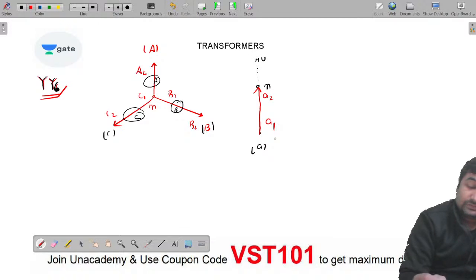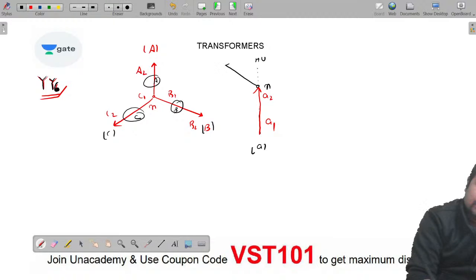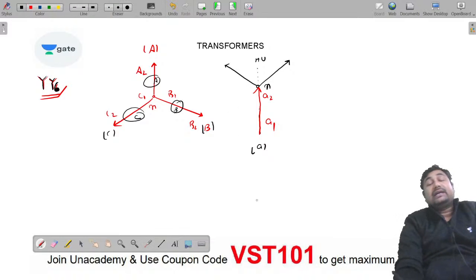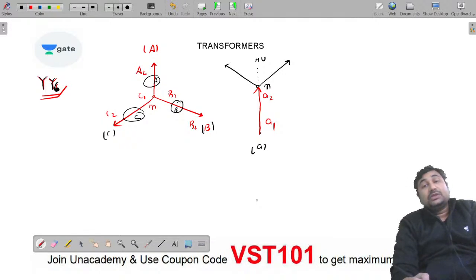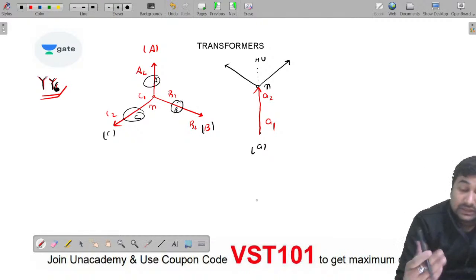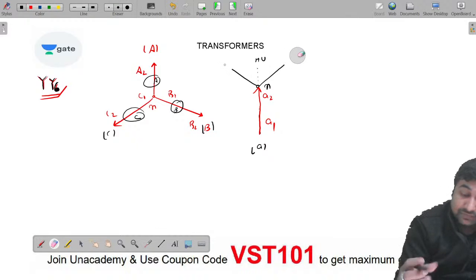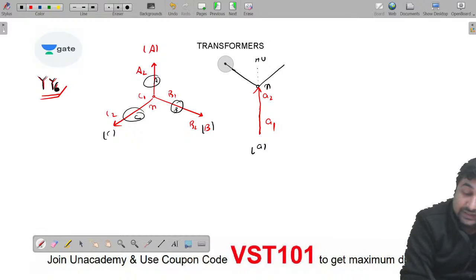Now keeping in mind that the LV side is in star, draw a line 180 degrees displaced, then draw another line 120 degrees displaced from that. All the phases are identical in a 3-phase transformer, so you have to keep that in mind - all the phases are identical in every respect. So the length of each line is the same.